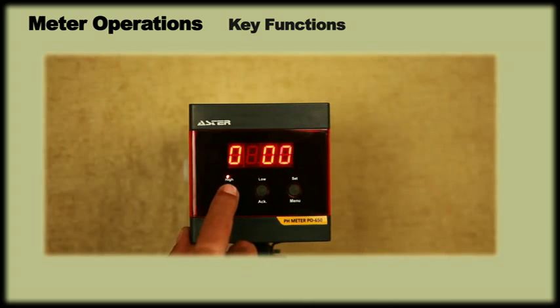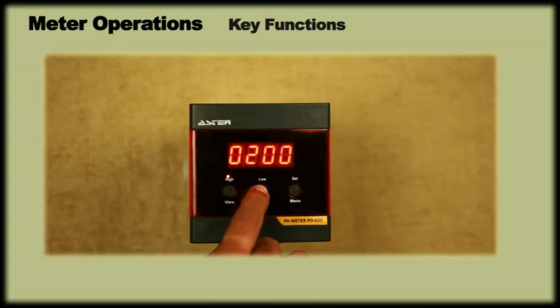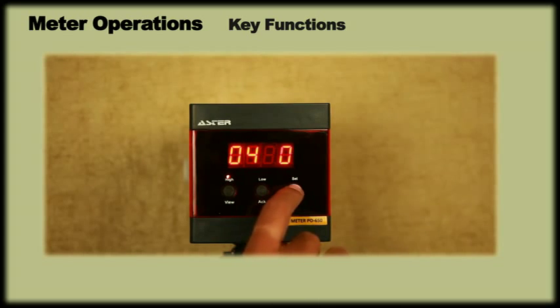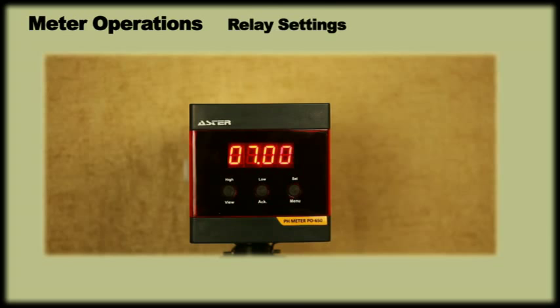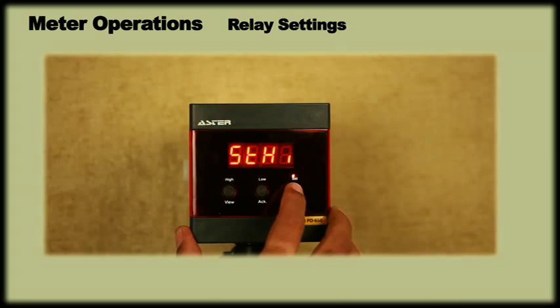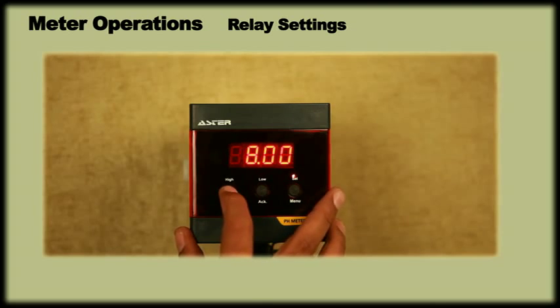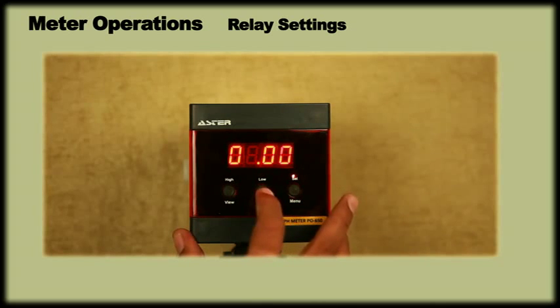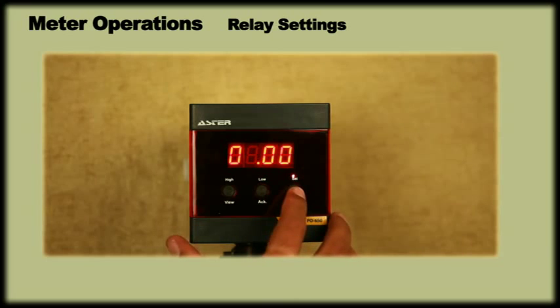While programming, the view key can be used to right shift, the ACK key for increment, and the menu key to enter and save the setting. How to program set point of pH. Once we press the menu key, it will show set high. Press the menu key, the display will show a previously set high pH value. Using ACK key and view key, we can set the required high pH value. For example, let us set high pH value as 9.00 and press menu to enter.